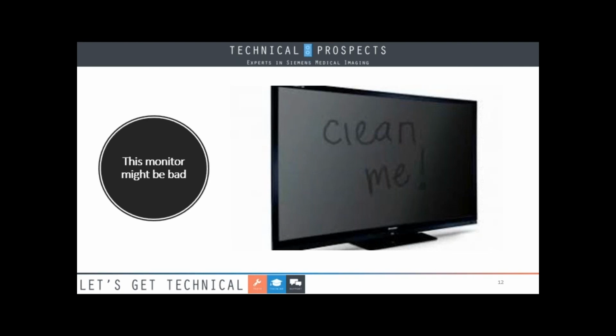If you have power, you see a default splash screen when the system boots up. If you do see a default splash screen, then the monitor has the capability to display images. One of the things I did when I was in the field was I carried a spare monitor. I could easily install it in place of the original monitor. If the monitor I brought works, then the original monitor is bad. If my spare monitor didn't work, then I'm checking the cables, the graphics cards, and the computer tower itself.